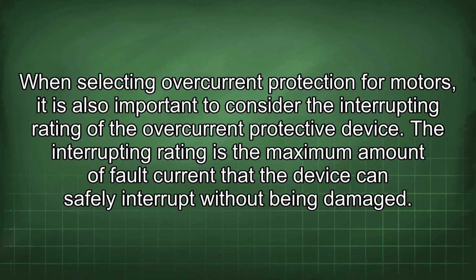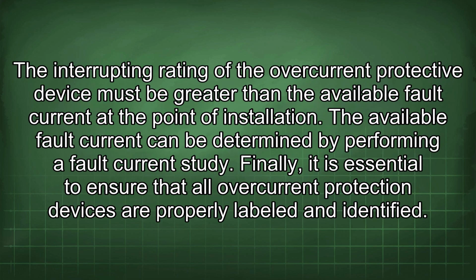When selecting overcurrent protection for motors, it is also important to consider the interrupting rating of the overcurrent protective device. The interrupting rating is the maximum amount of fault current that the device can safely interrupt without being damaged. The interrupting rating of the overcurrent protective device must be greater than the available fault current at the point of installation. The available fault current can be determined by performing a fault current study.